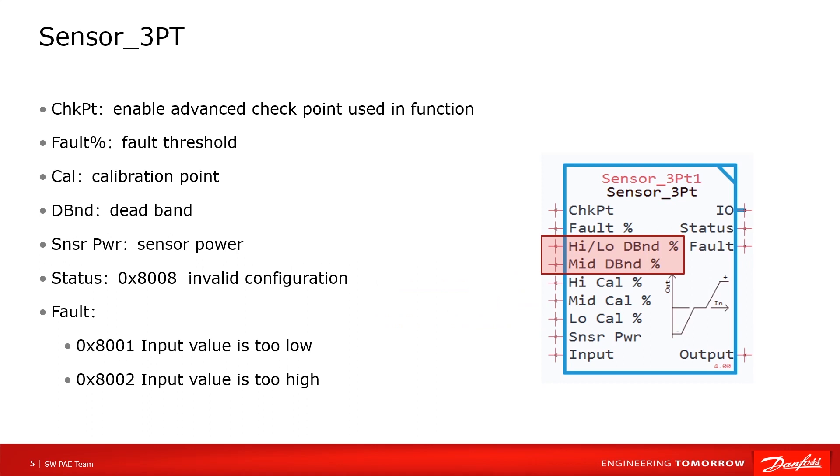Dead band. High and low dead band and middle dead band. The purpose of dead band is to define the range where outputs stay at 100%, minus 100%, and zero. Sensor power is the reference value of input signal, generally set to supply voltage of input device. Input is the signal from input device.